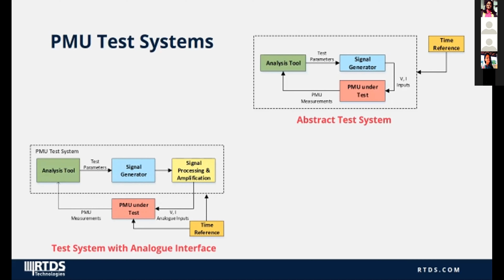Next, consider a more practical test system. This system has three functional units: test system, PMU under test, and time reference. The test system and PMU are synchronized to the time reference. Here, the analysis tool calculates and delivers the theoretical test parameters to the signal generator, which generates time domain waveforms accordingly. Depending on the nature of the signal generator and the PMU's input interface ratings, some signal processing and amplification might be required. Finally, the analysis tool collects PMU measurements from the PMU and compares them against the theoretical values to determine error quantities.